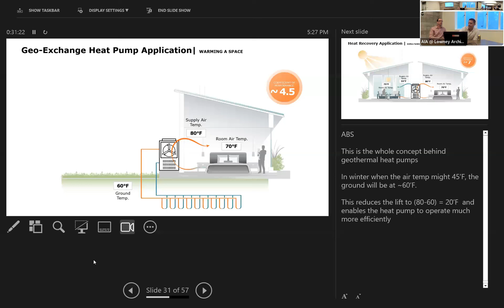And then here's the next one. This is like the holy grail of efficient heat pump applications. And it's where, in all of the previous examples, only one side of the heat pump has been providing a benefit. So for example, when it was in cooling mode, you had a beneficial side cooling the space. The other side was just rejecting unwanted heat to atmosphere. Okay. Now this is an example where you've got a building that has a simultaneous demand for heating and cooling. So on the left, you've got a room receiving low angle easterly sun and it needs cooling. Okay. And on the right, it's receiving no solar radiation and it needs heat.